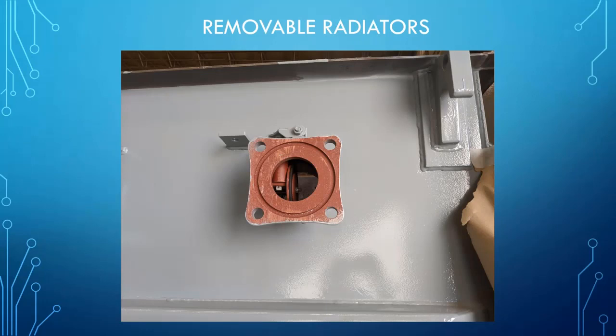In most small transformers, the radiators are just welded onto the tank. If I'm a consulting engineer and I'm going to put a transformer indoors, I would prefer to specify removable radiators. And here's why. In case the transformer fails and must be removed to be worked on, and let's assume it's something in the core and coils that has failed, it's very difficult to move around a liquid-filled transformer with the radiators attached. They're usually large units. They're 75, 85, could be 100 inches deep, and they will not go through a standard doorway. If it were me, I would always specify removable radiators if the transformer is going in a building.